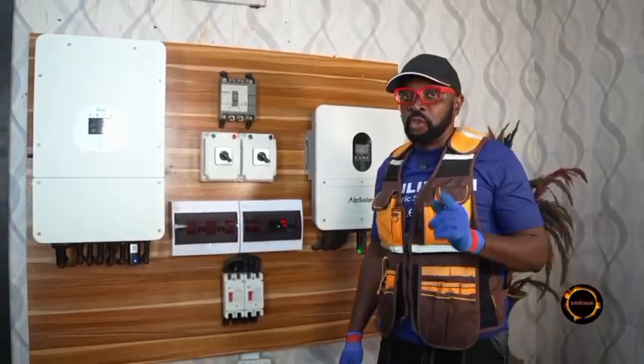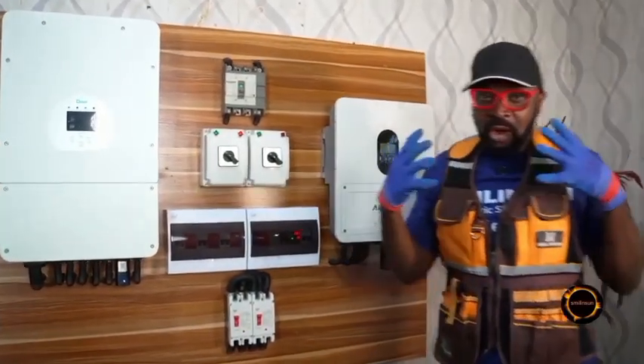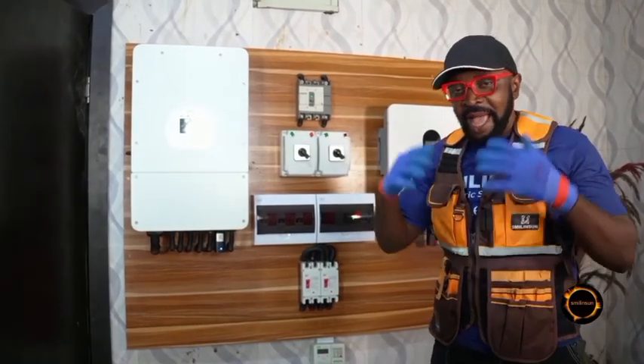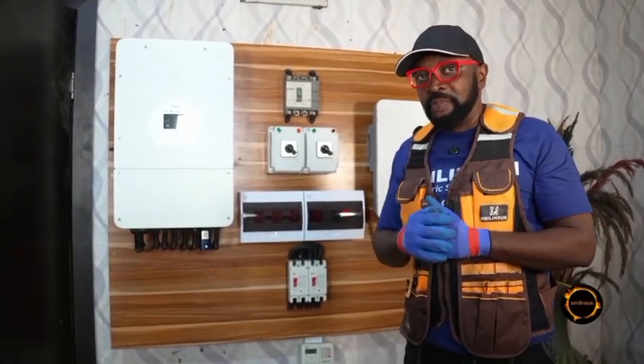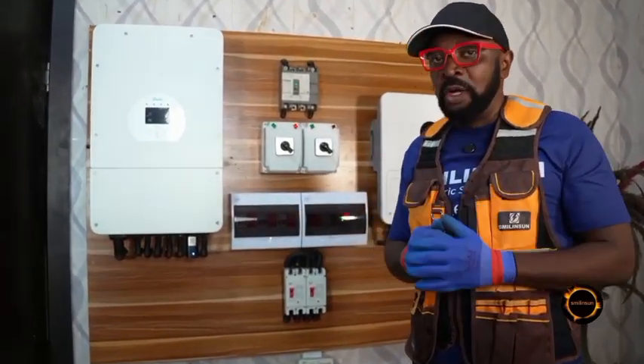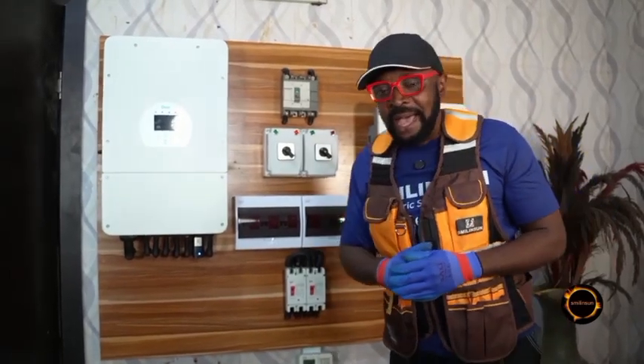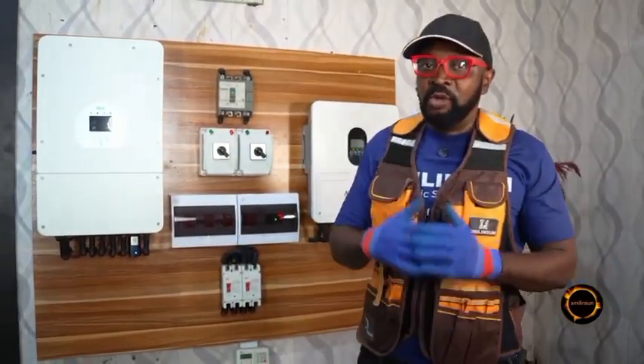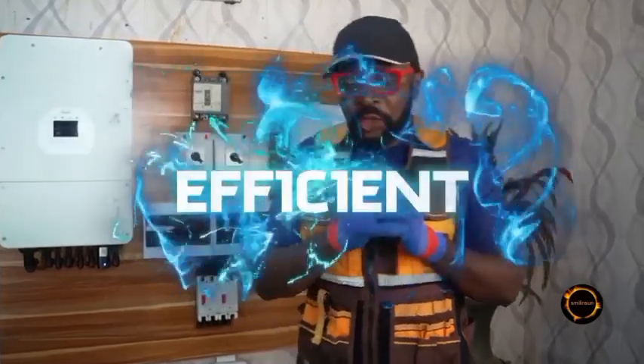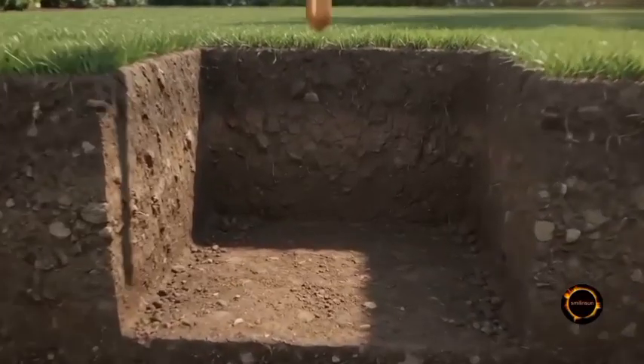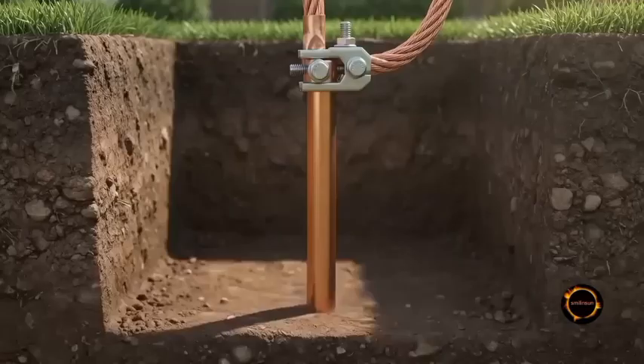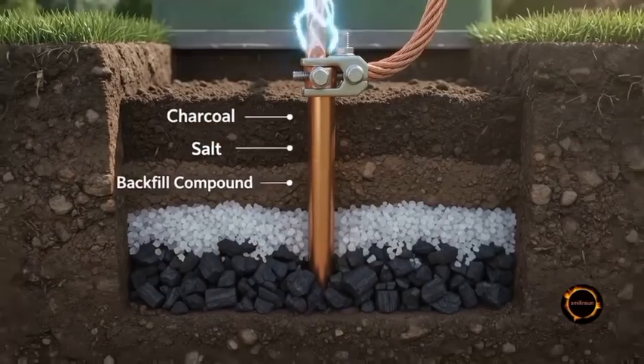One of the things that you should also keep in mind is that your earth installation is not a one-off thing. Most people are under the illusion that after doing your earth installation, it's a one-off thing and it's over. No, after a while, you're meant to come back and test its resistance, because every now and then you need to ascertain how efficient your earthing installation is. Most people think, once I've done it, that's it, I'll never have to do it again.